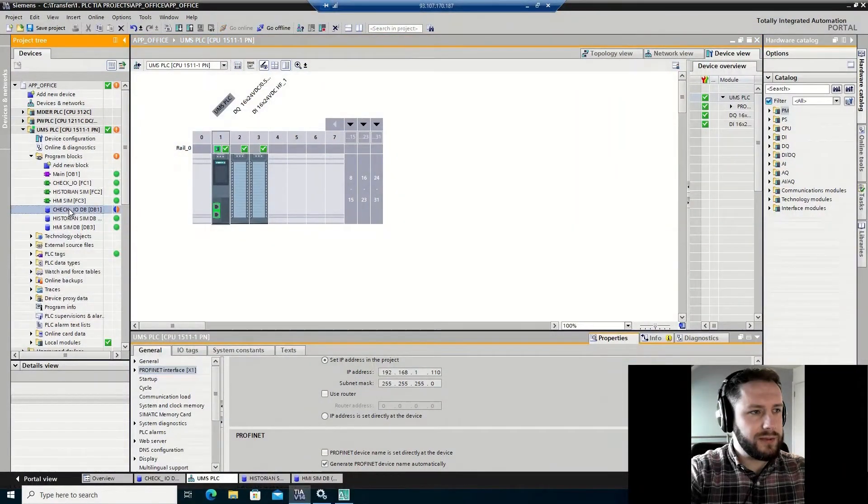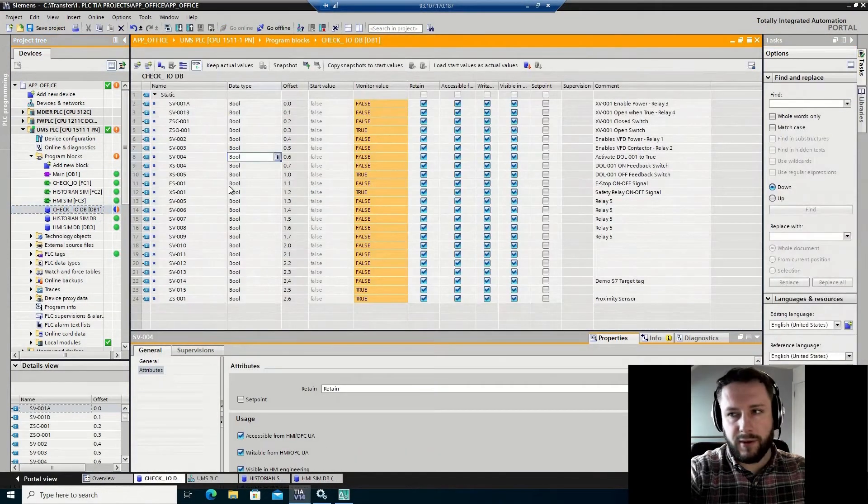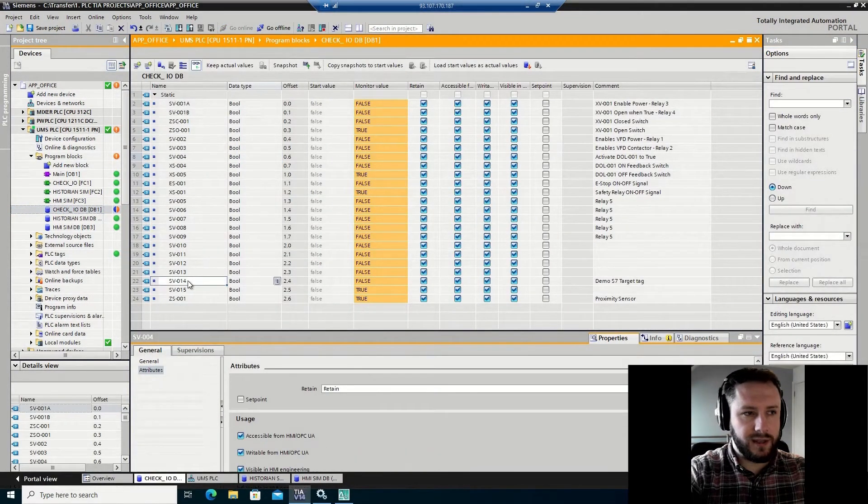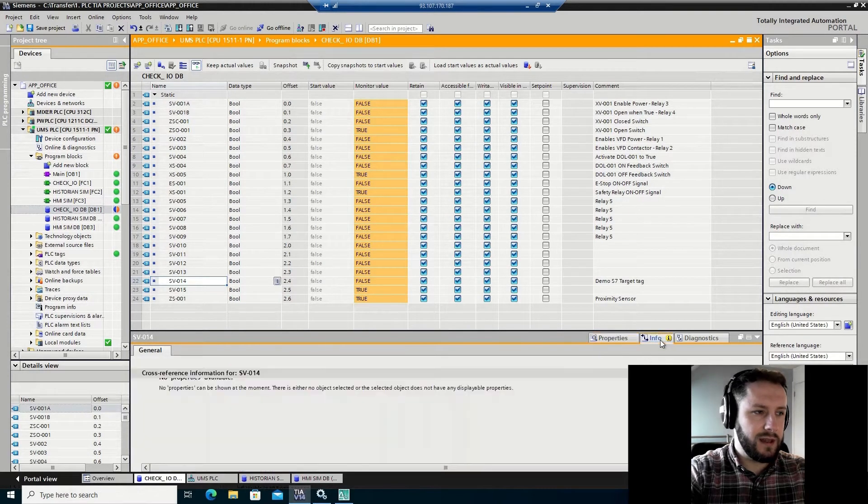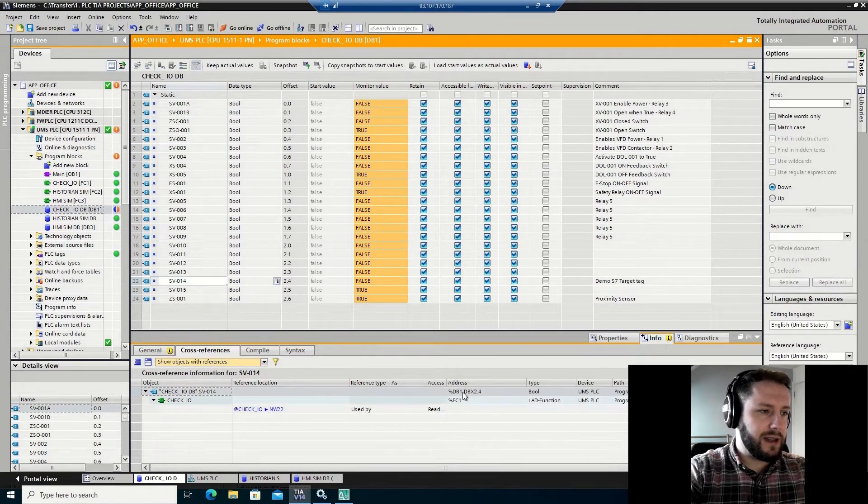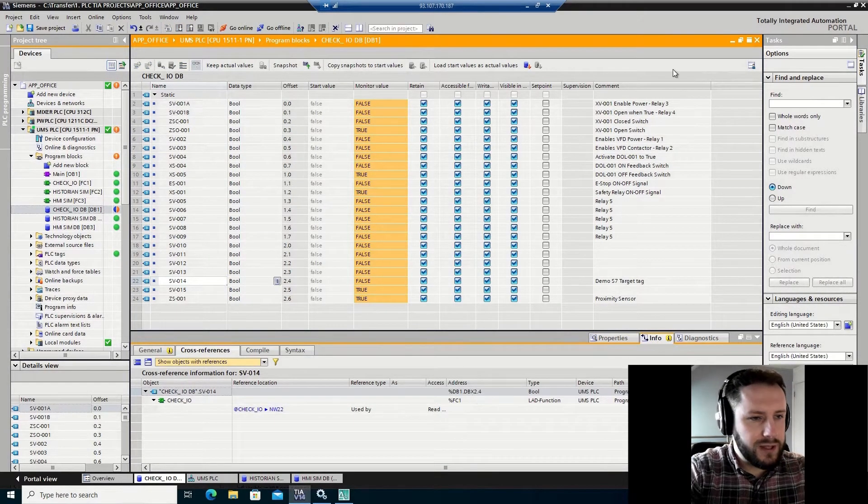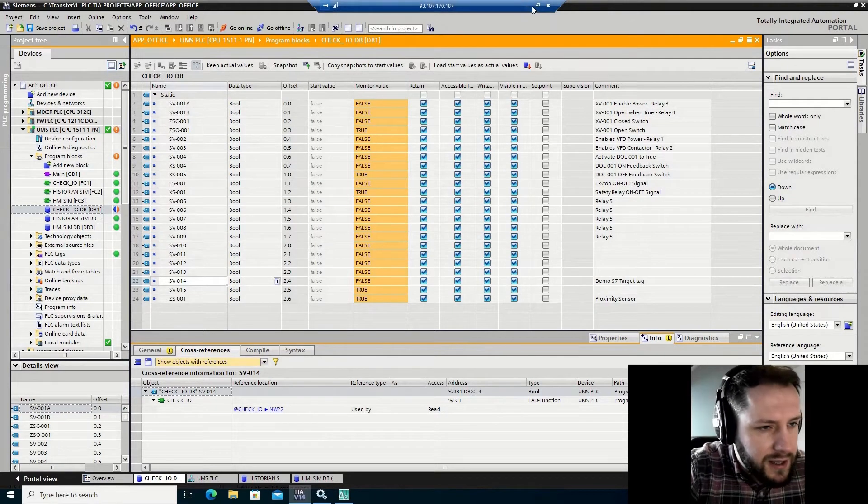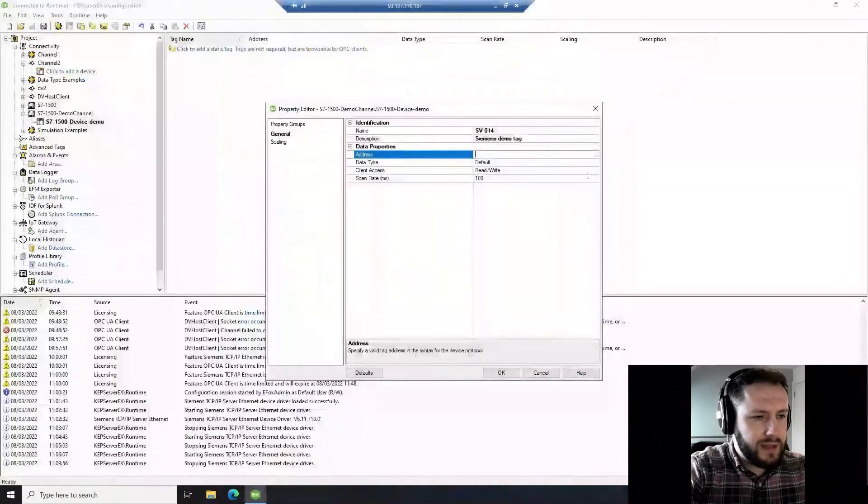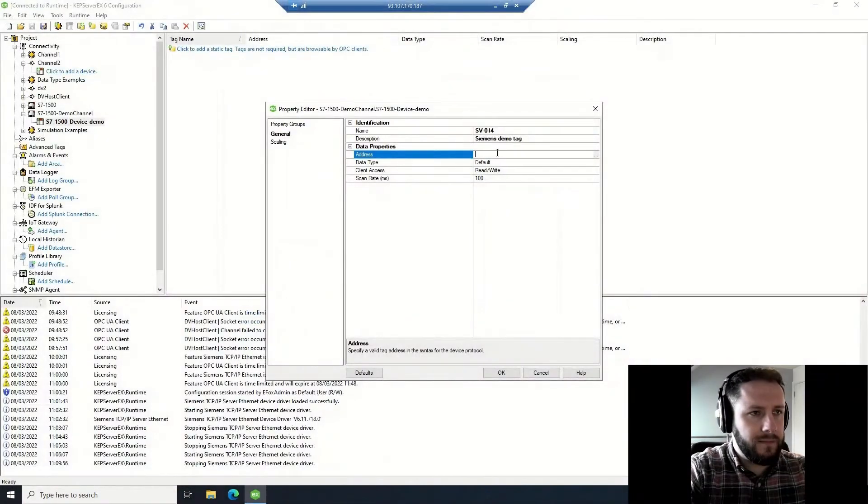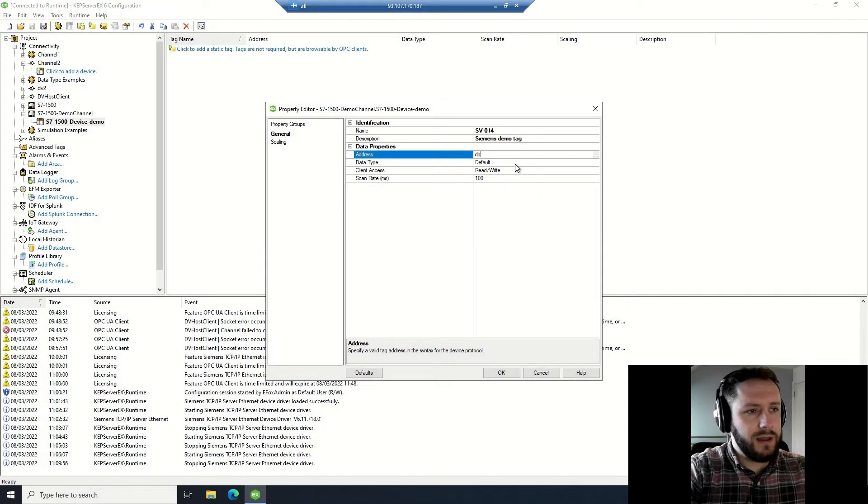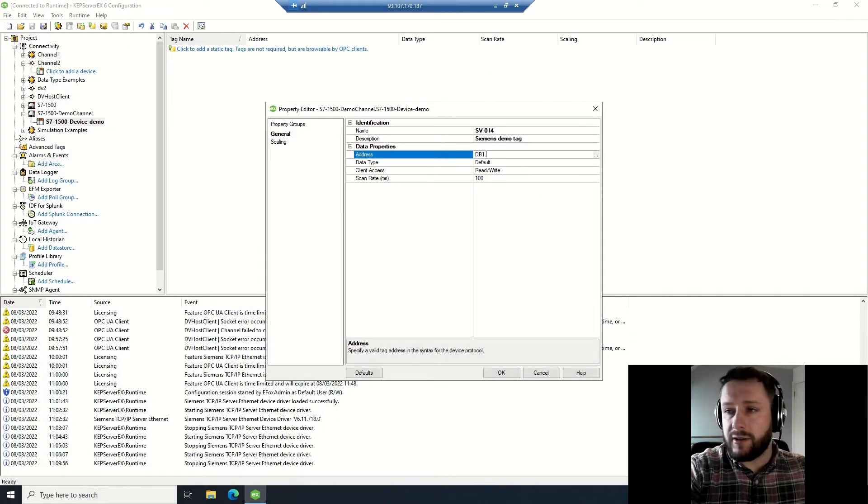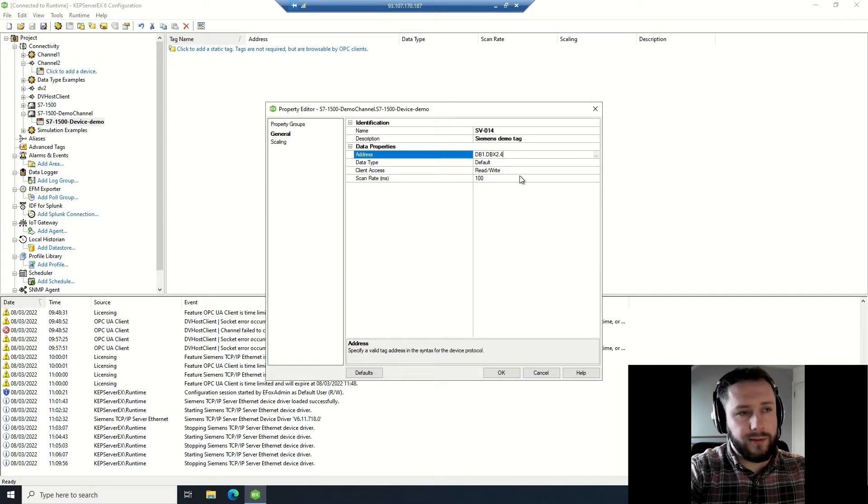Excellent, okay. So I'm going to open up TIA again, I'm going to go into the data block where the signal is going to reside. It's going to be a Boolean signal. You'll see here I have it called SV014, and I have a description there on the right hand side: Demo S7. And then down on the bottom I clicked properties and I viewed its data block address, which is DB1.DBX2.4.